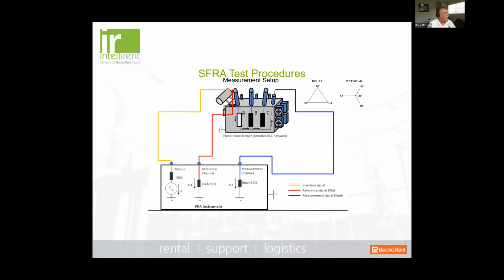The test procedures are fairly simple, as we see here. You have an output of your voltage. Okay, you have a reference channel to make sure that what you're putting in is exactly what you're using comparatively in your measurement. Okay, and then you have your measurement channel. And this is a typical configuration on a 2-winding delta-Y transformer.